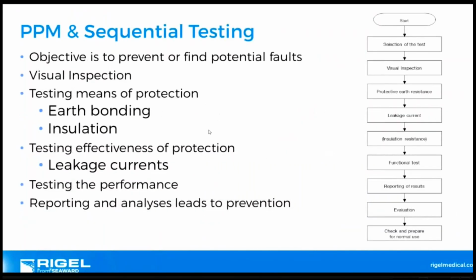How is it different to 60601? Because we start to look for the objective, which is to prevent and find potential faults. We have a visual check. We have almost like a sequential order of how you should perform a preventative maintenance schedule.